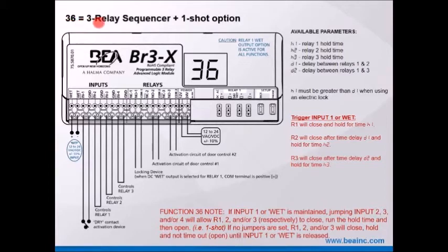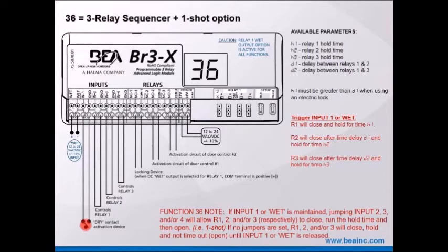Function 36 equals a three-relay sequencer with a one-shot option. Input one and ground is normally used to activate or start a sequence. The key difference on function 36 is that if you make a dead short or put a jumper on input two, three, or four, that will control relay one, two, and three respectively as a one-shot function — meaning that output will run the hold timer and expire and then relax when the hold timer is done.